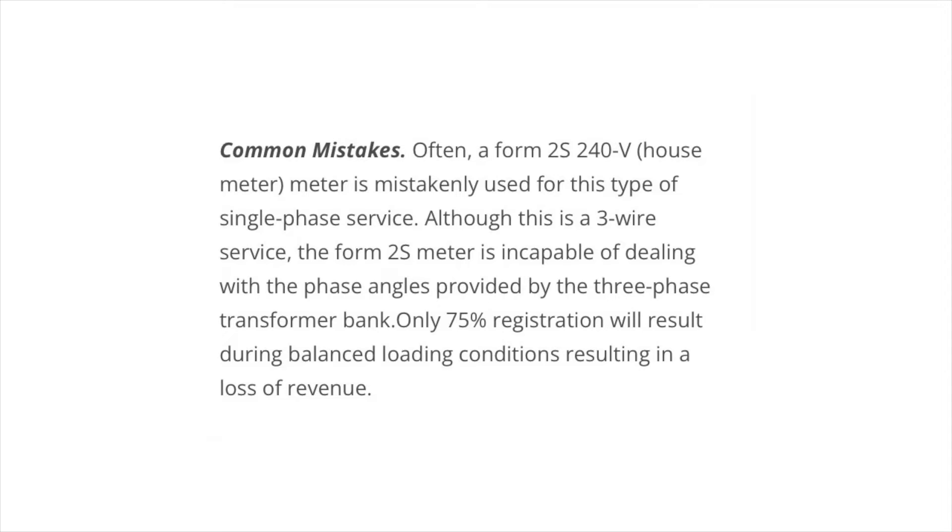One of the most common mistakes we find: servicemen will accidentally plug in a form 2S meter at this single phase service. And although it's a three-wire service, the form 2S meter is not capable of dealing with the difference in the phase angles provided by the transformer bank, and it'll result in only a 75 percent registration during balanced load conditions. So we're losing revenue in this application. It's very important that we put the correct form with the correct service type. Being that this is a Y system, it needs a Y 12S application.